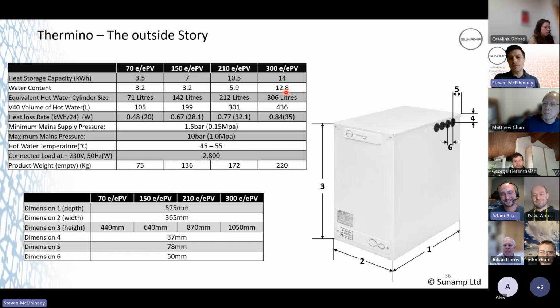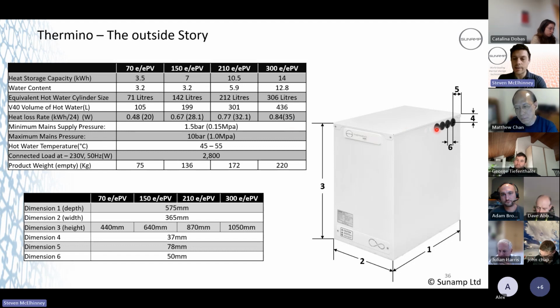So if the customer's got a 300 with a full charge and they want to go away for a week's holiday, they could turn it off on the timer, not use any electricity, just to top it up, and they'll still come home with some hot water. Albeit it won't be full capacity, but a lot of that's to do with the pipework being lagged as well. Another thing we sometimes get is called thermal siphoning. If you've got the pipework coming out and then going up vertically from the unit, you can get heat loss by means of convection. So in an ideal world, you want to come out and go down to stop that from happening.